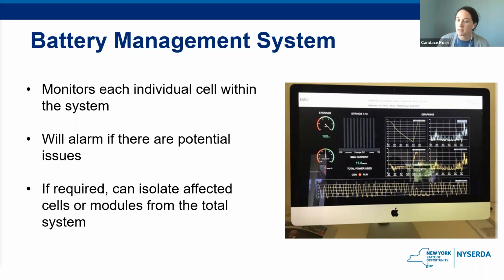The battery management system can monitor each individual cell within the system and make sure it's operating properly. If there is any issue outside of normal cell, module, or rack operating characteristics, it has the ability to isolate the cell to avoid it damaging additional cells. So not only is it watching and making sure everything is operating properly, it can also manage and deal with any uncharacteristic issues that occur within the system.